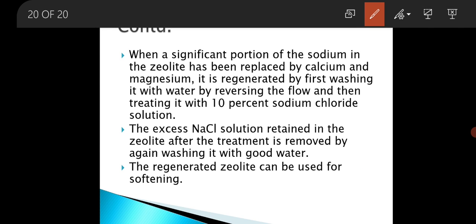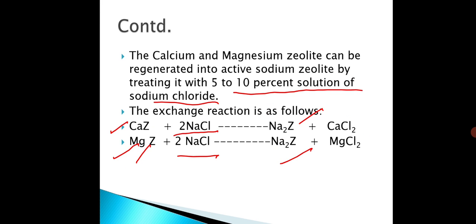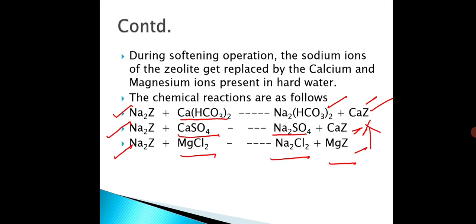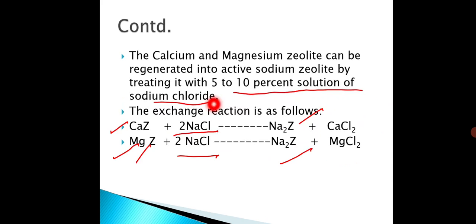When a significant portion of the sodium zeolite, Na2Z, has been replaced by calcium and magnesium, it is regenerated by first washing it with water by reversing the flow, and then treating it with a 10 percent solution of NaCl sodium chloride. After regeneration, the sodium zeolite is again formed.